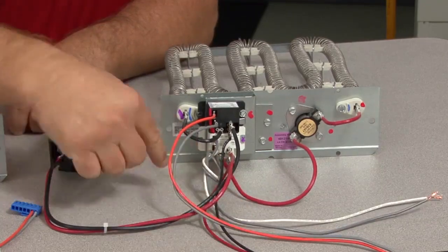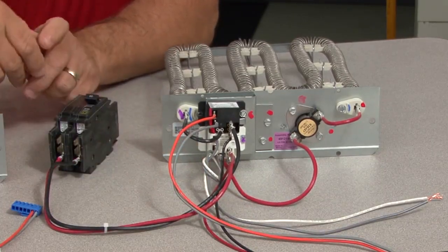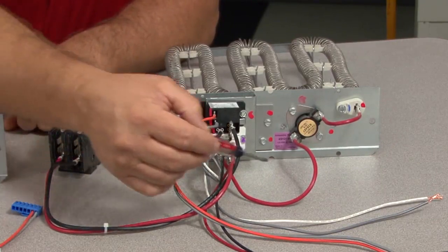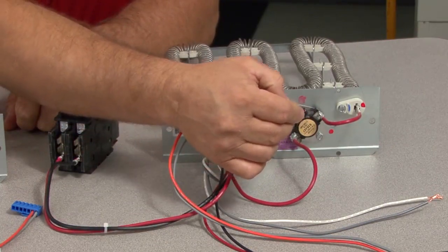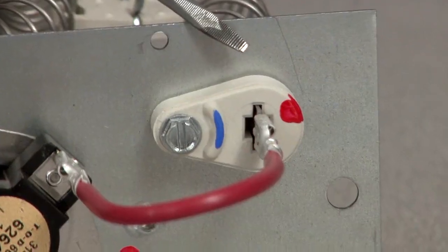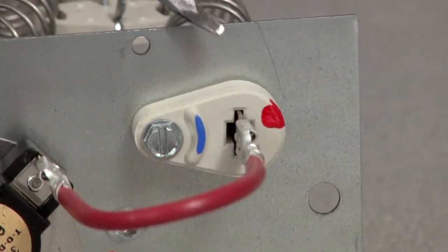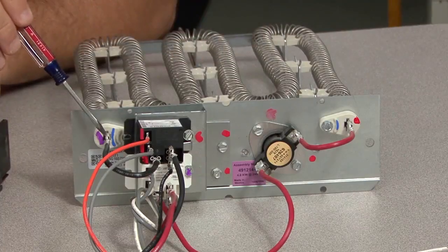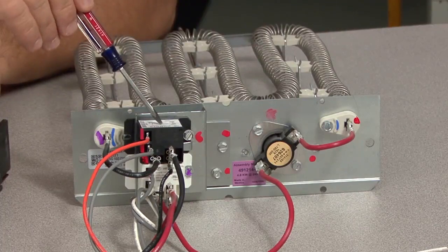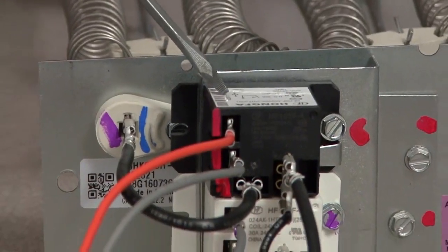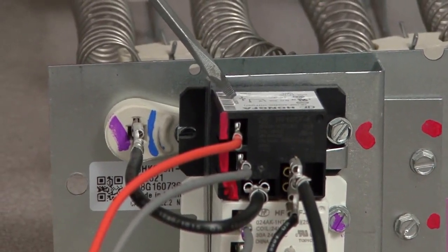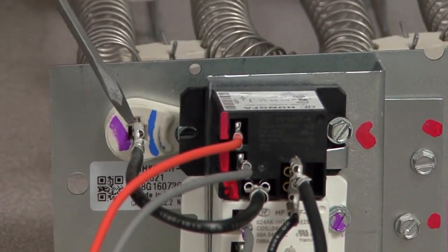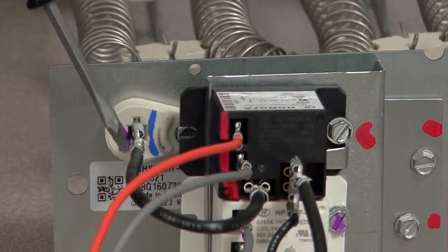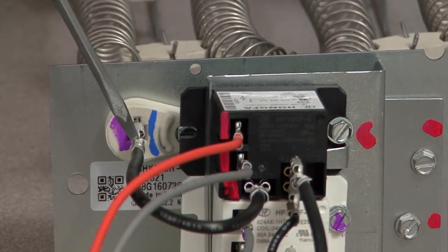We're going to energize that white relay, and the white relay is controlling the power going into the other side of the element. The black wire going into the element is controlled by the DC relay. That's what happened here. The Underwriters Laboratory said, we can no longer build heater kits that only switch off the power to one side of the element, and that's what the H6 heater kit did.